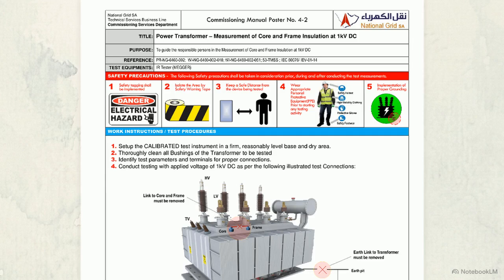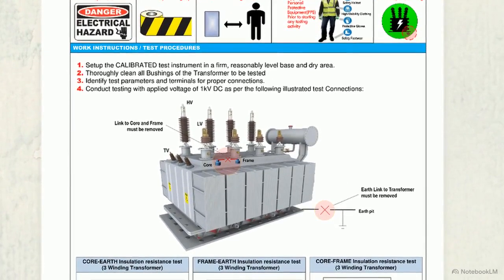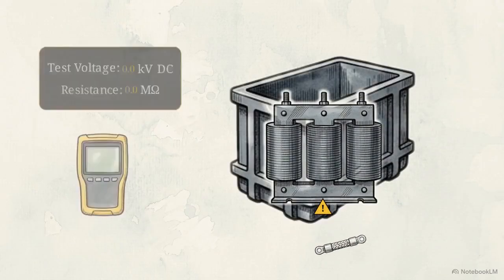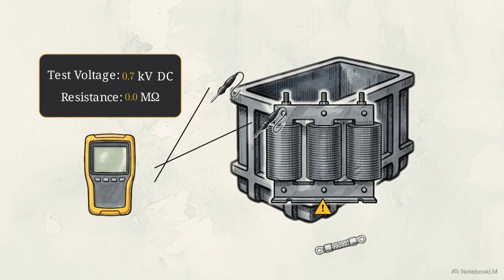This schematic highlights the procedure for core and frame insulation testing at 1 kV DC. Notice the explicit requirement. The links connecting the core and frame to earth must be physically removed to prevent a false ground reading. We inject the test voltage to verify that the core and the clamping frame are electrically isolated from the main tank. The acceptance criterion demands an insulation resistance exceeding 10 megohms.